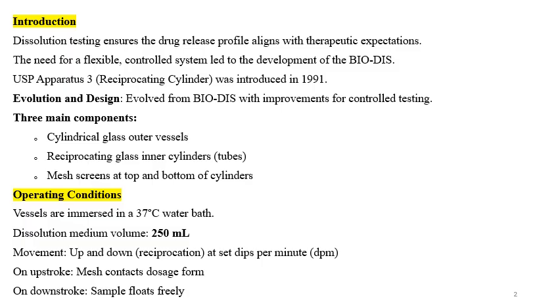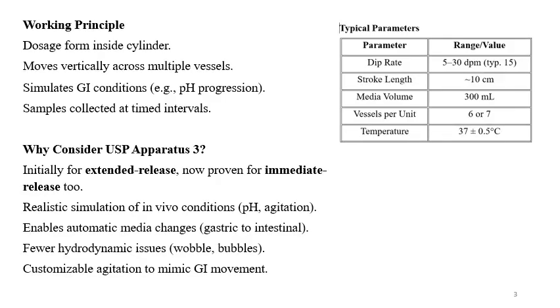Dips per minute is the speed parameter for this apparatus. Typical parameters include a dip rate of 5 to 30 dips per minute, with a typical operating DPM of 15. Stroke length is around 10 cm. Media volume is up to 300 ml, with a typical volume of 250 ml. There are 6 vessels per unit, and temperature is maintained at 37°C.